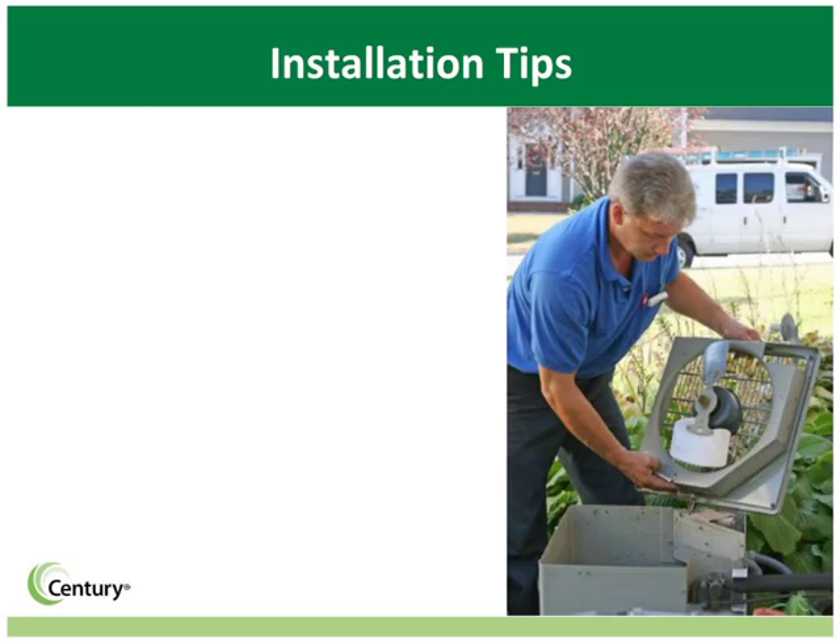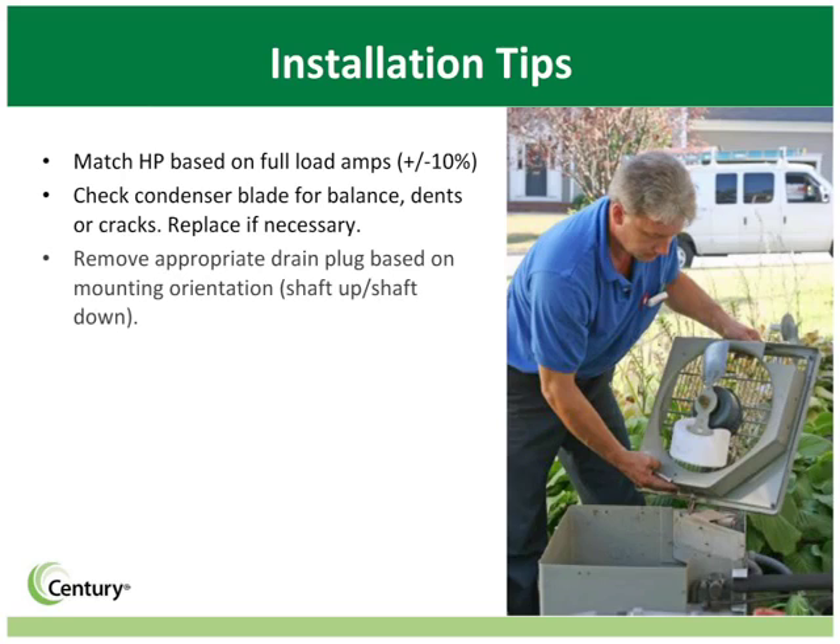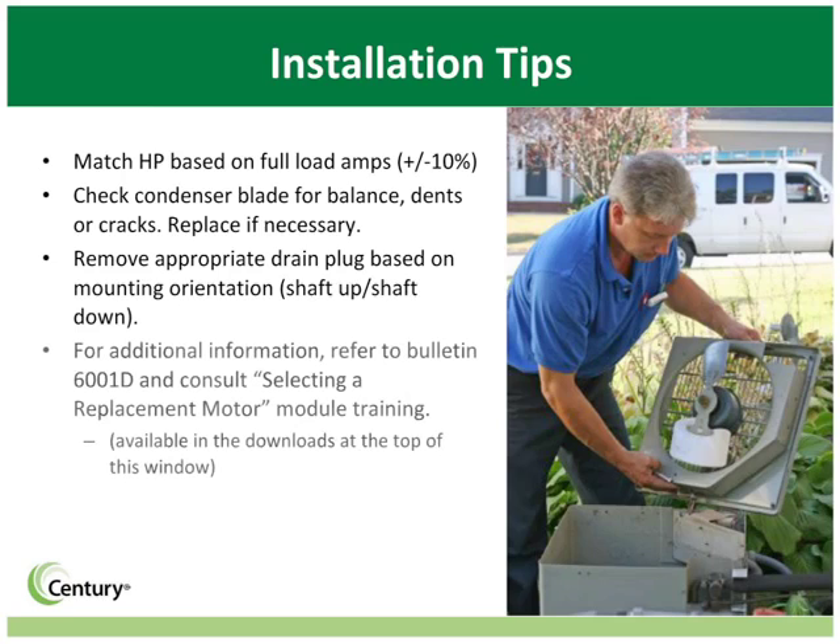When replacing an old motor with a 4-in-1 motor, follow the normal installation steps and keep the following points in mind. Be sure to match the horsepower based on full load amps, plus or minus 10%. Also check the condenser blade for balance and dents or cracks, and replace the blade if necessary. You'll also need to remove the appropriate drain plug — removing the plug allows moisture to escape and increases the life of the motor. For additional information about 4-in-1 motors and installation, see Bulletin 6001D or consult the Selecting a Replacement Motor module training.